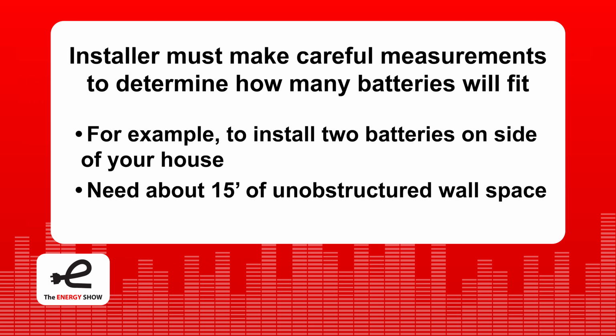It's tricky, so your installer has to make careful measurements to determine how many batteries will fit. If they don't, and say 'we're going to sell you 2 batteries, don't worry, there's room,' then when the engineer gets out there to measure it, they find out there's only room for 1 battery on this side of the house, and the other battery has to go all the way around to the other side - which is expensive because of the extra wiring needed.